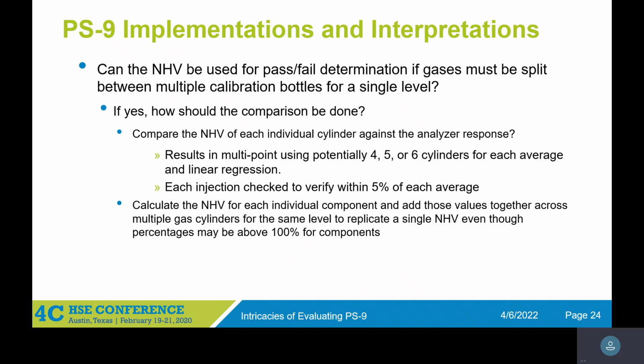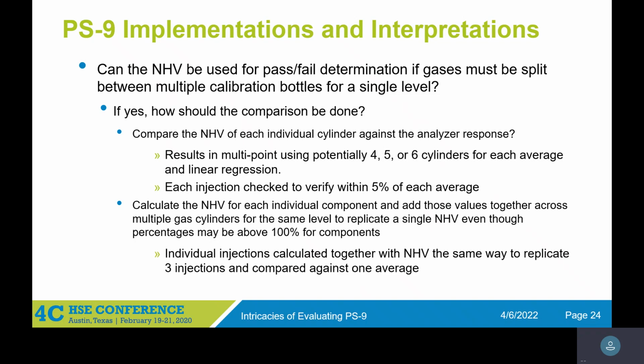And then the other option we've seen is we calculate the net heating value for each of those individual components and add those together across multiple gas cylinders to kind of replicate a single net heating value, even though the percentage of those gases might then be above 100%. And that kind of then replicates just the 3 injections as we were doing before, and 3 averages instead of upping the number of averages that you have.